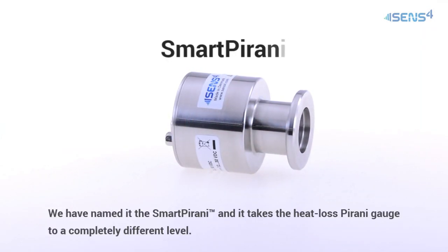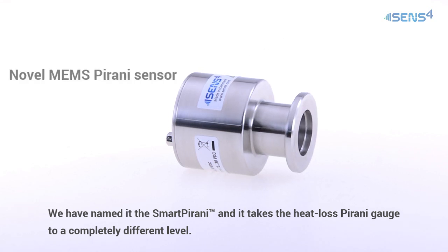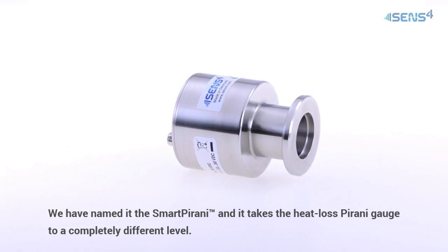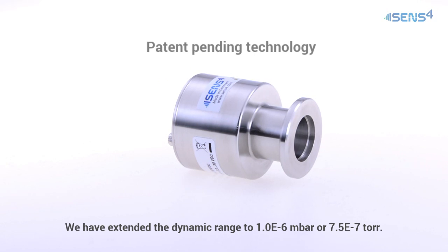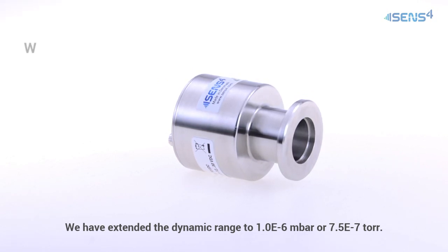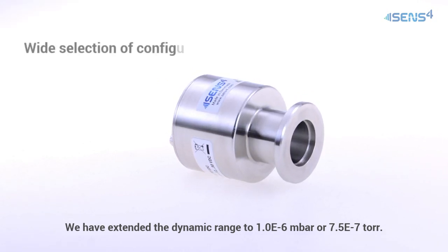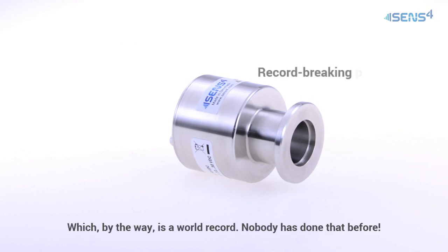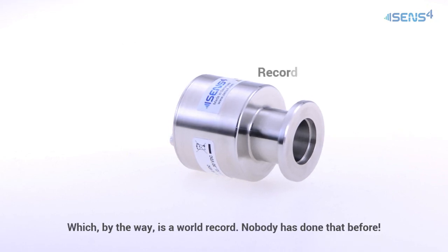We named it the SmartPirani, and it takes the heat loss Pirani gauges to a completely different level. We have extended the dynamic range to 1E-6 millibar, or 7.5E-7 torr, which by the way is a world record. Nobody has done that before.